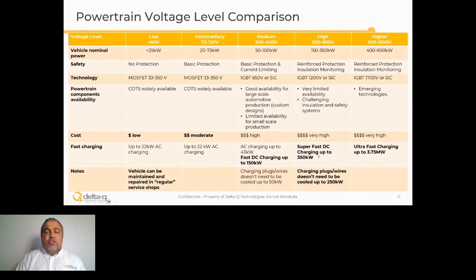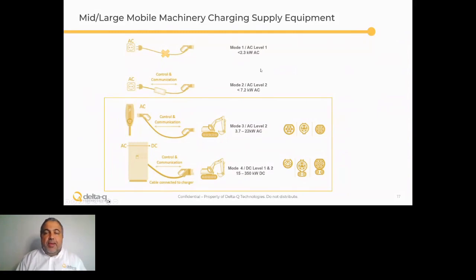For mid and large size industrial machinery, the most reliable and safe solution for charging is using standard EV charging stations. What's known as Mode 1 and Mode 2, enabling charging up to 7 kilowatts, are not very applicable to these systems, because they either lack the safety mechanisms or do not provide the high power necessary for the applications. What is suitable for these applications is Mode 3, which is AC charging, and Mode 4, which is fast DC charging.